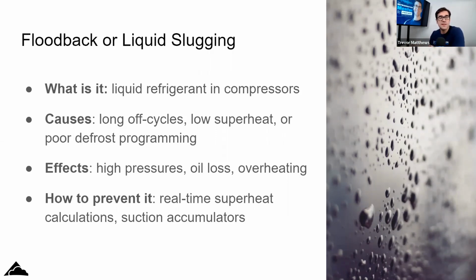The older systems, some people are starting to add more of these sensors, like for the airflow. There's a big one, people: it's airflow, airflow, airflow. If you don't have airflow, the temperature of that evaporator coil drops right off, and then you start to get liquid going back.